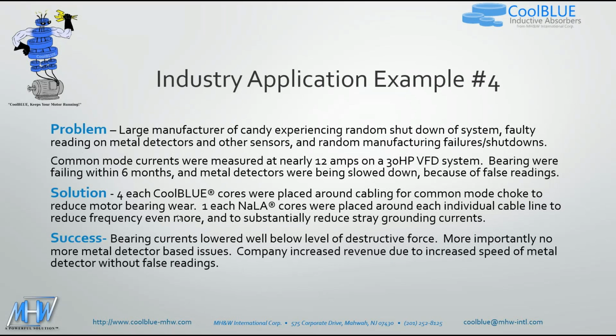So we installed 4 CoolBLUE cores placed around the cabling for common mode choke to reduce the motor bearing wear. One each NALA core was placed around each individual cable line to reduce the frequency even more and to substantially reduce stray grounding currents. The bearing currents lowered well below the level of destructive force. More importantly, no more metal detector-based issues. The company increased revenue due to the increased speed of the metal detector without false readings.